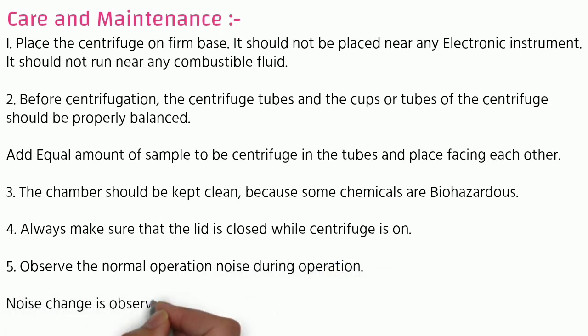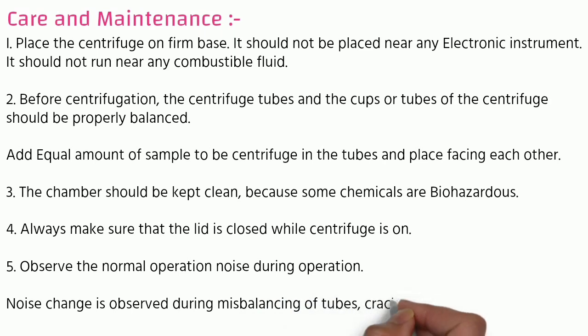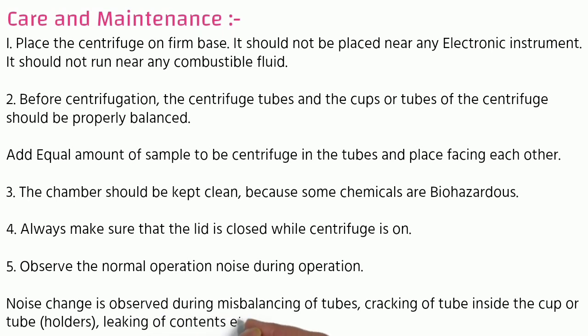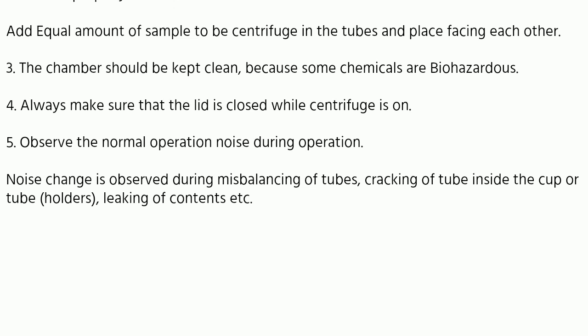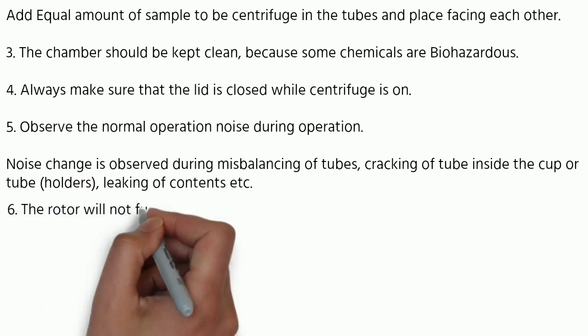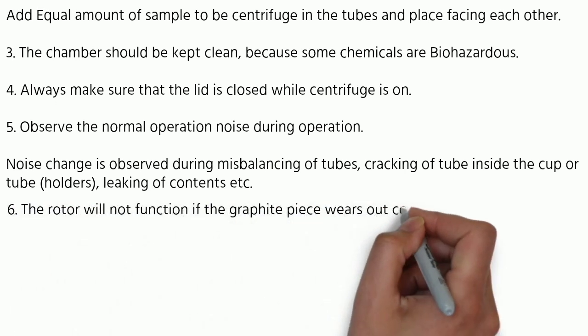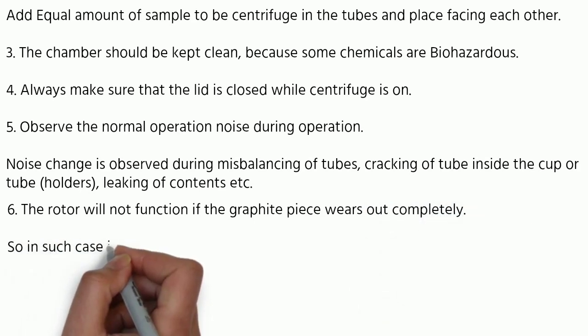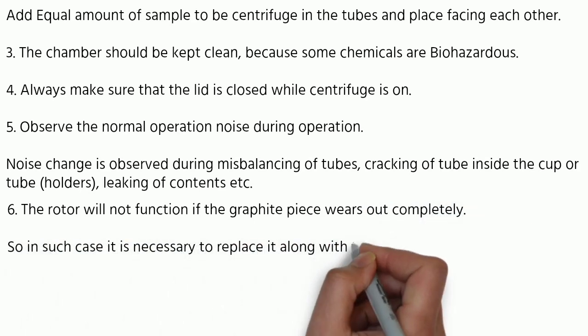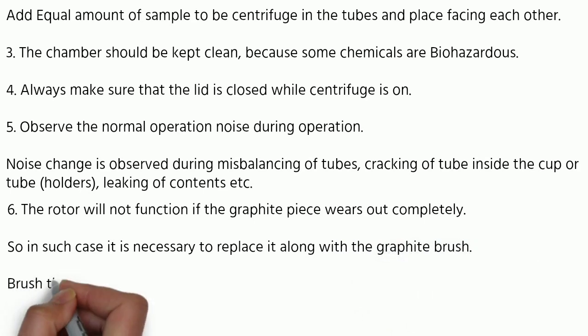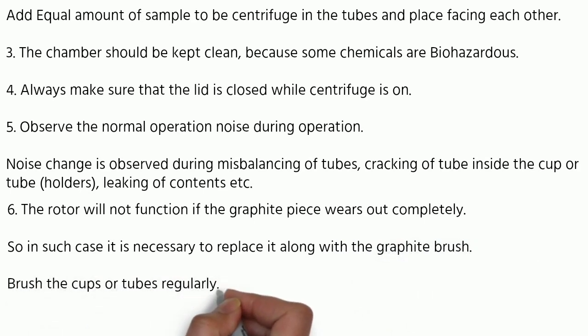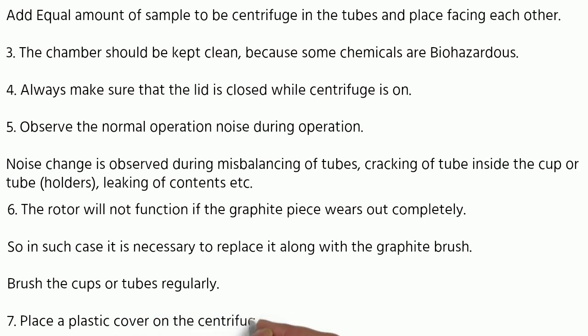Observe the noise during operation — a noise change indicates misbalancing of tubes, which could cause cracking of a tube inside the cup or holder, or leaking of contents. The rotor will not function if the graphite piece wears out completely; in such a case it is necessary to replace the graphite brushes. Brush the cup or tube holder regularly, and place a plastic cover on the centrifuge when not in use.